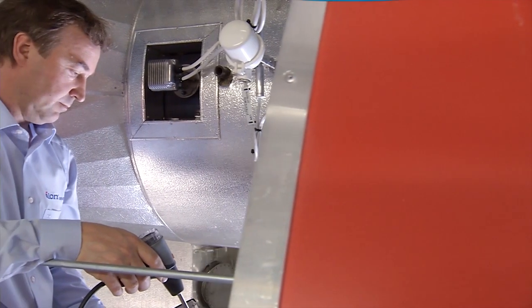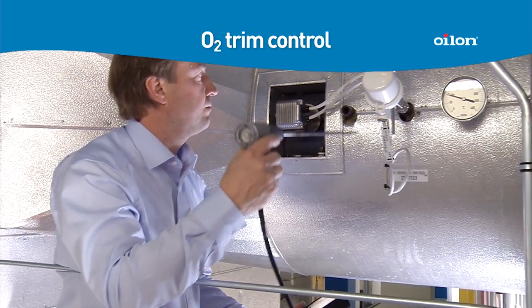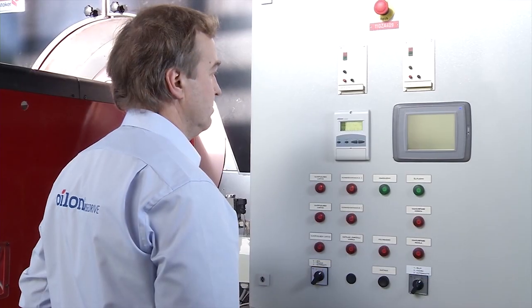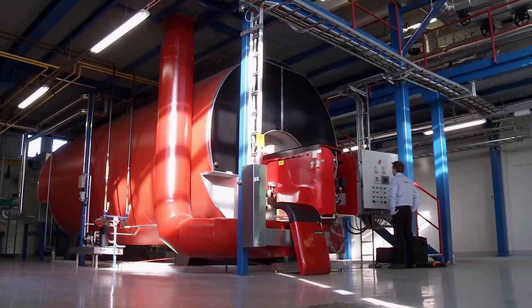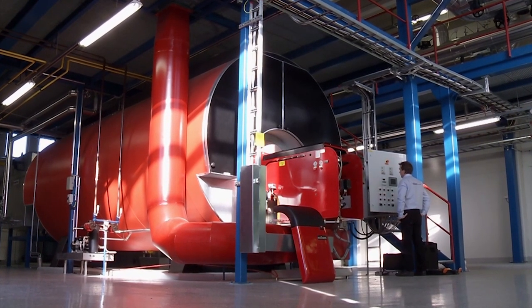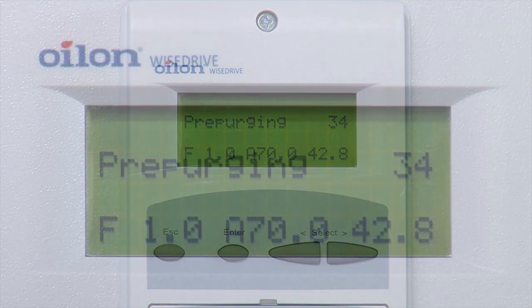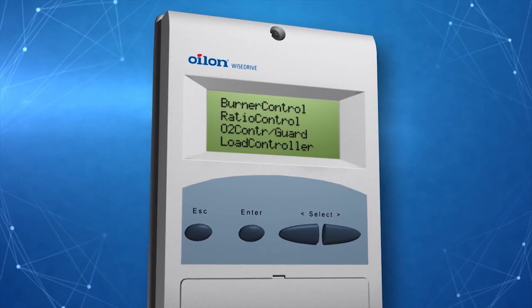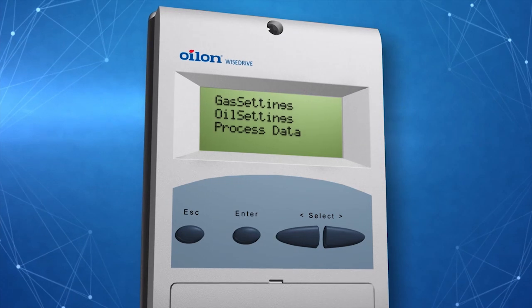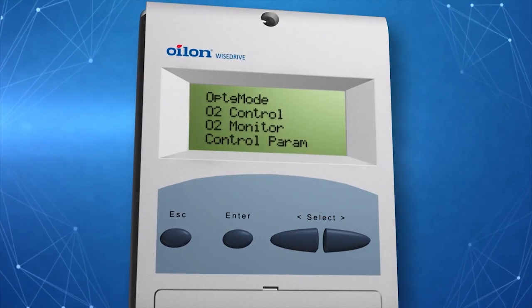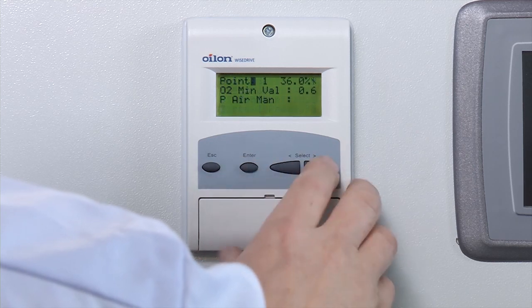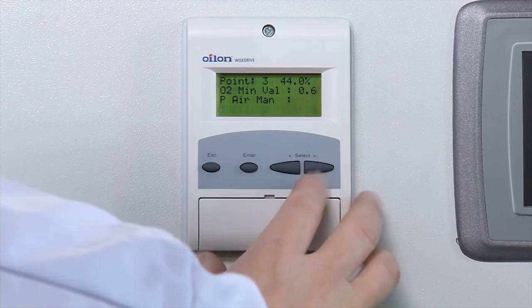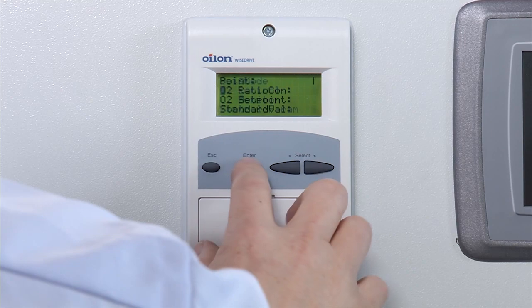The ratio of oxygen control is essential in reaching the optimal air-fuel ratio, maximising combustion efficiency and minimising emissions. The oxygen ratio control can be set after setting the capacity ratio curve. It is set separately for both fuels and they are independent from one another. Start by setting the oxygen minimum value control. Oxygen minimum values can be entered directly to curve points — the first line shows the curve point number. Enter the residual oxygen level in percentage points, then exit by pressing escape and confirm values by pressing enter.